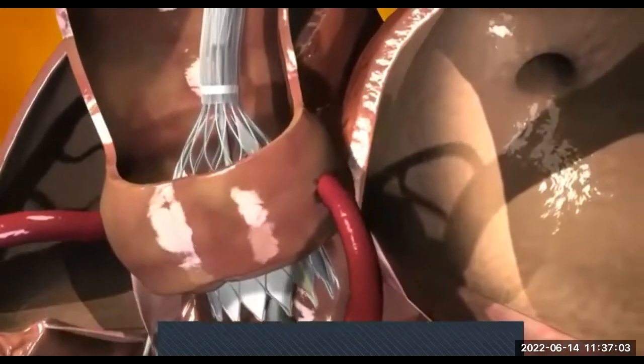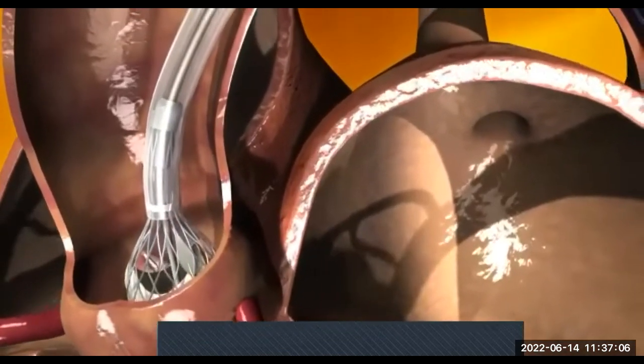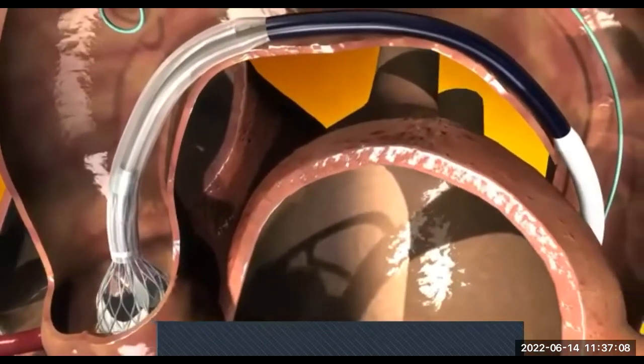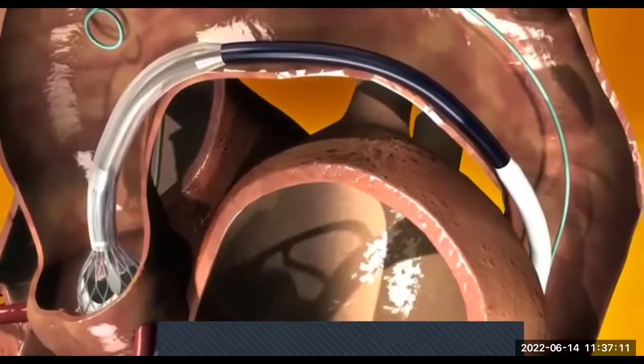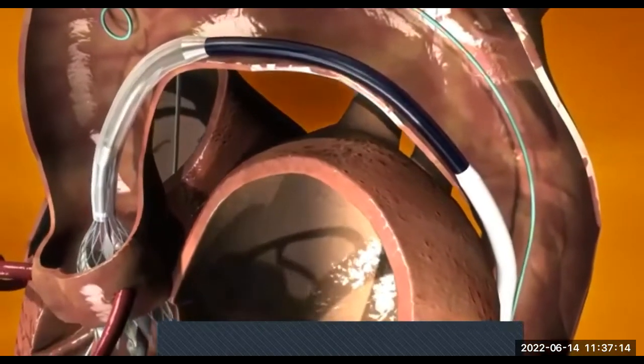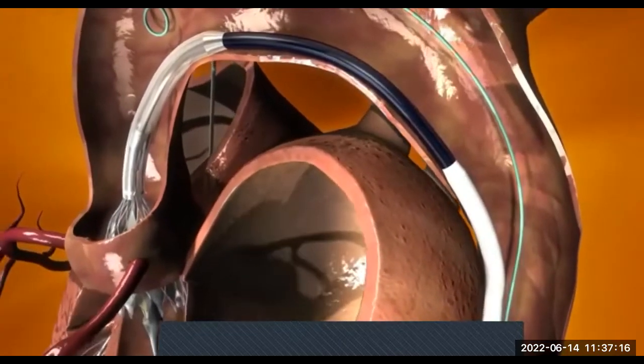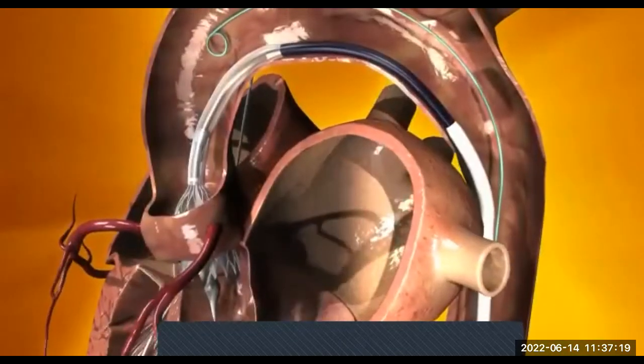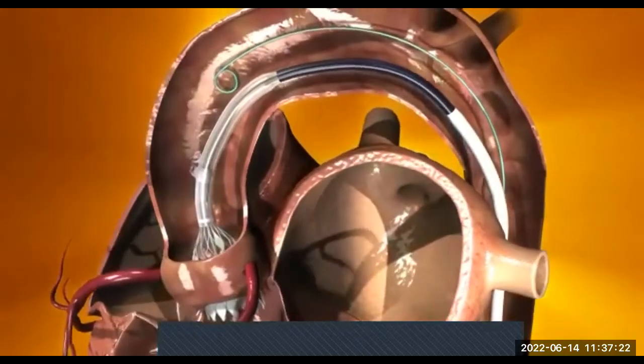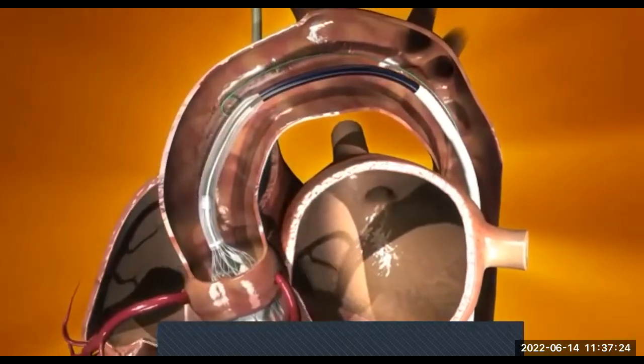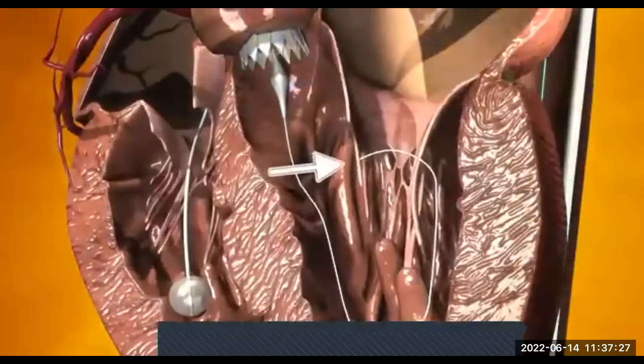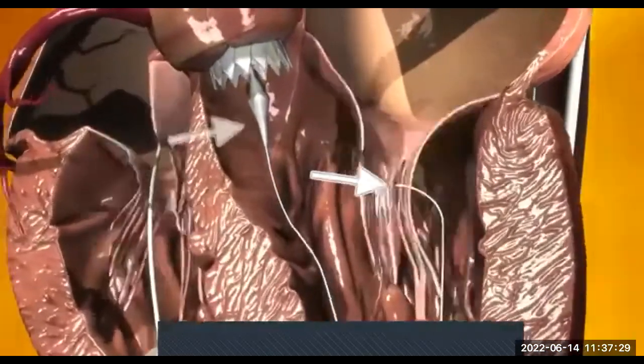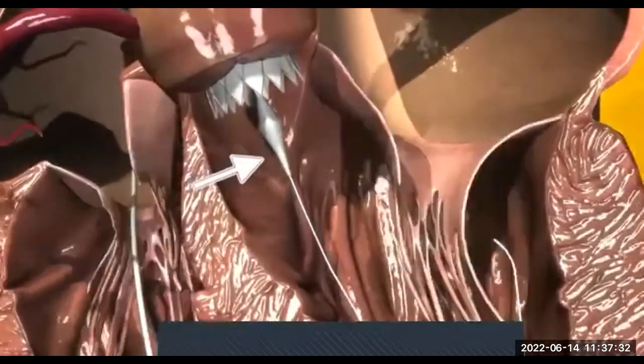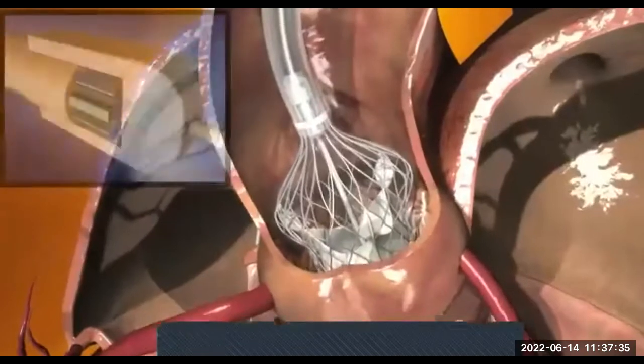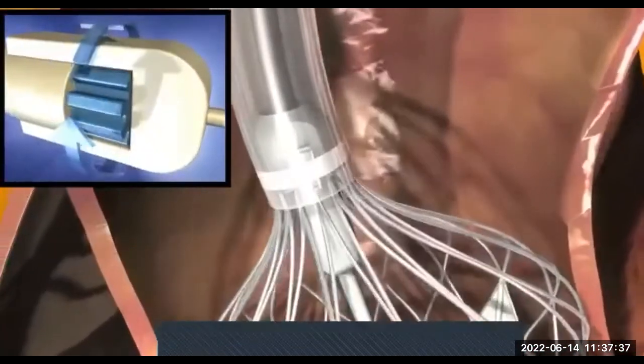When satisfied with valve placement, observe the catheter position in the arch to identify the presence of tension in the system. If the position of the catheter is along the inner curvature of the aortic arch, this may indicate the presence of tension in the system, placing an antegrade force on the valve. If tension is suspected, relieve the force on the valve by slightly pushing on the catheter just prior to valve release and retracting the guide wire until the distal tip of the delivery catheter centers inside the inflow aspect of the frame. Once tension has been released from the system as needed, turn the micro knob until both loops disengage.